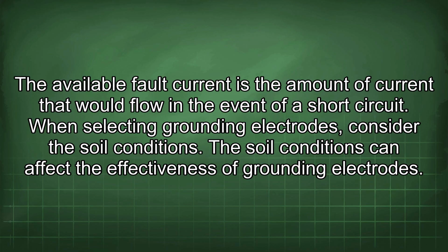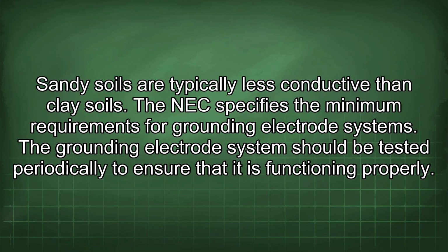When selecting grounding electrodes, consider the soil conditions. The soil conditions can affect the effectiveness of grounding electrodes. Sandy soils are typically less conductive than clay soils. The NEC specifies the minimum requirements for grounding electrode systems. The grounding electrode system should be tested periodically to ensure that it is functioning properly.